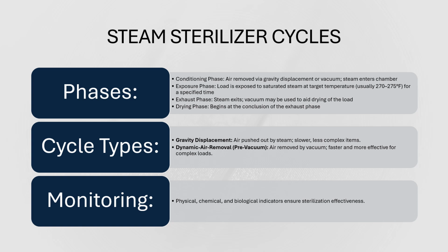The biological indicator is the ampoule that has the bacteria that we use to make sure that the autoclave is doing its job. That is done after the autoclave is done. You'll take that biological out, you'll crush it, and you'll incubate it to see if that cycle killed that bacteria that's in that ampoule. If it has killed it, it's a negative result, which means it's a good cycle. If it failed, we have to document that it failed and rerun that whole complete cycle.